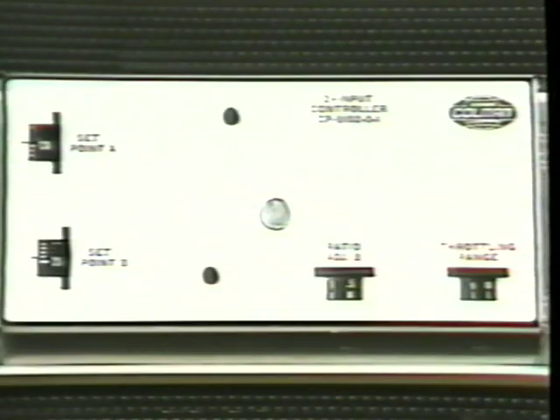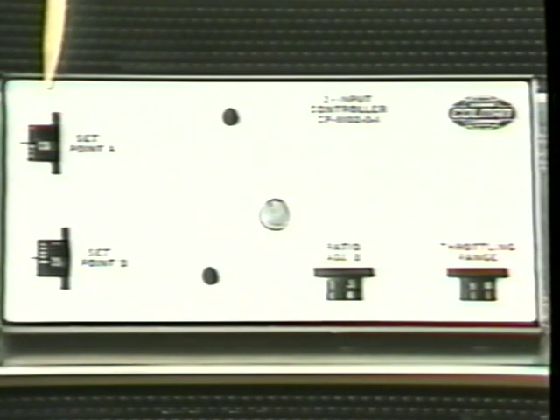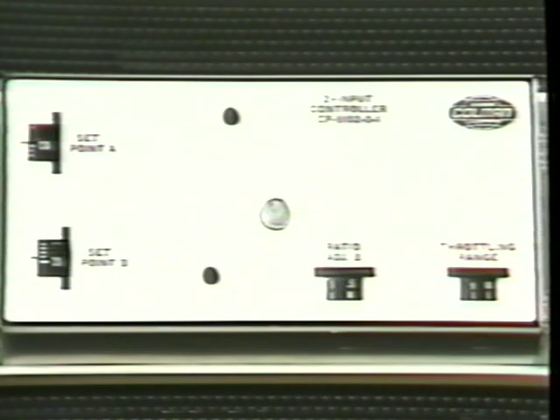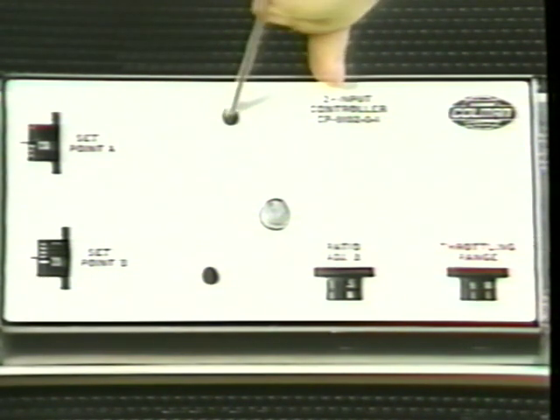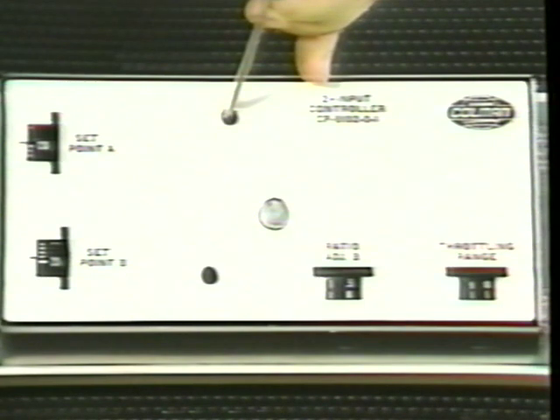The cover accessible adjustments are Set point A. This is the set point for control bridge A. It's adjustable from 20 to 120 degrees Fahrenheit, but whatever its setting, that is the variable value the controller attempts to maintain. Calibration A. This is an access port allowing controller recalibration without removing the cover. Below is the calibration pot for bridge A.